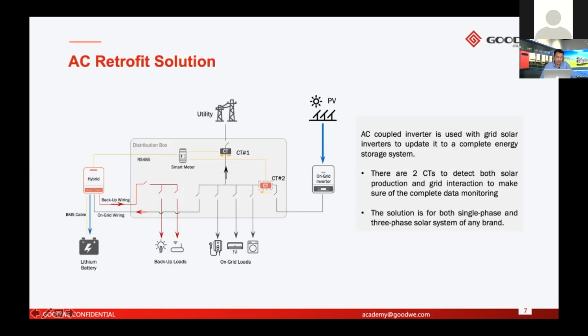Another difference is when the grid fails in AC retrofit systems. If the grid fails, the on-grid inverter cannot work, so the PV cannot work. So for AC retrofit systems, only the battery and backup loads are available. Only the battery supports the backup loads. This is the only operation mode, and this is the difference.